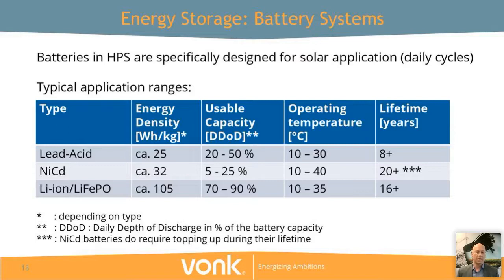It has the highest energy density, and you can also discharge it further than other batteries. I should say something more about the daily depth of discharge—that's the percentage of the capacity you can use per day, so up to what percentage you can actually discharge your batteries without jeopardizing their lifetime.